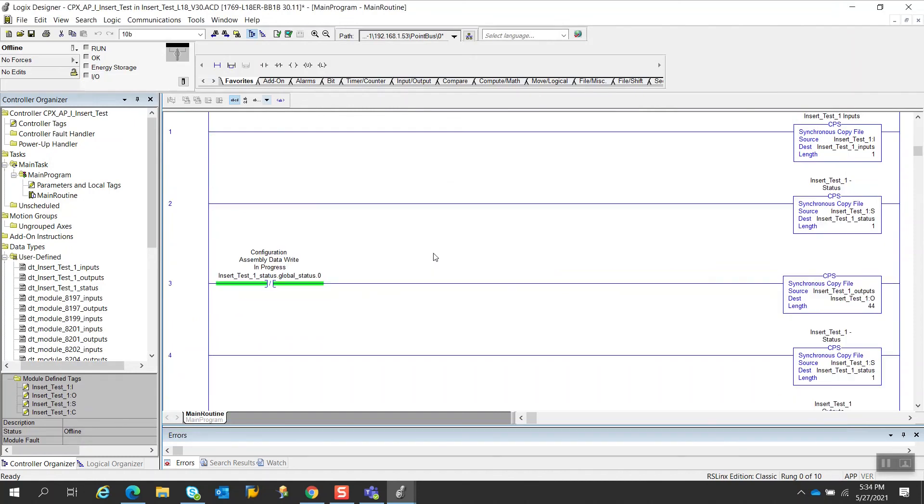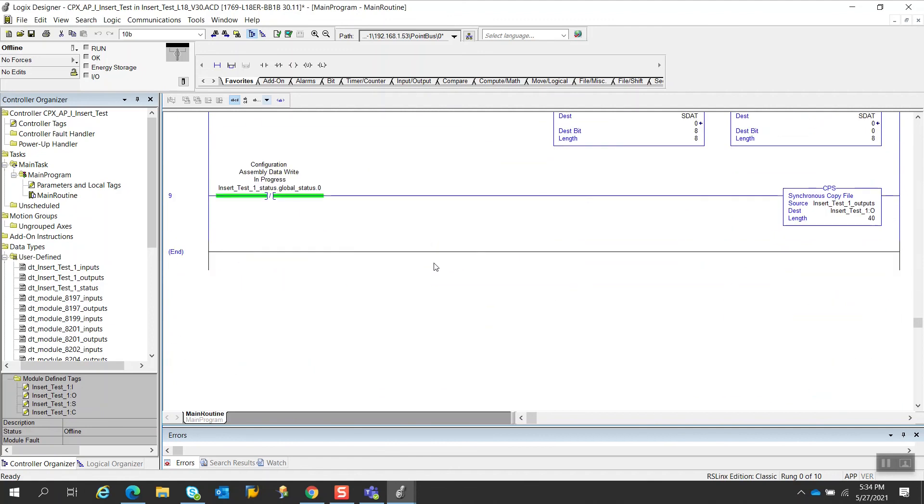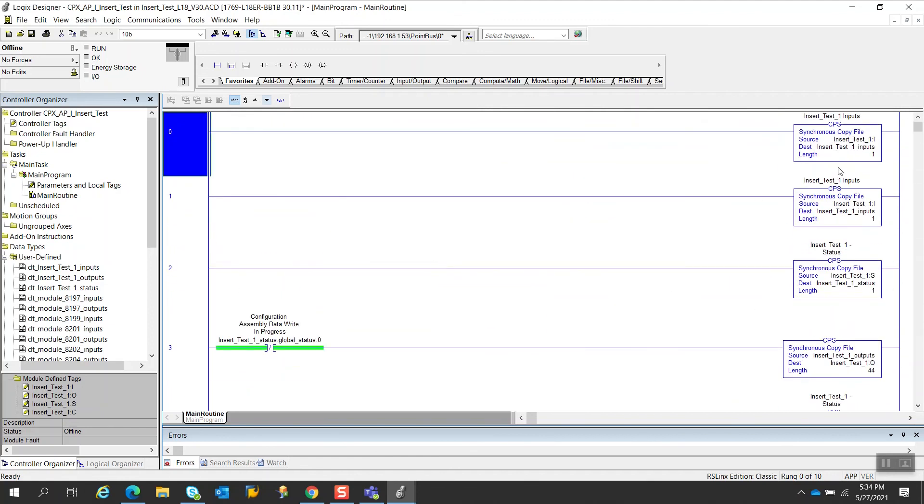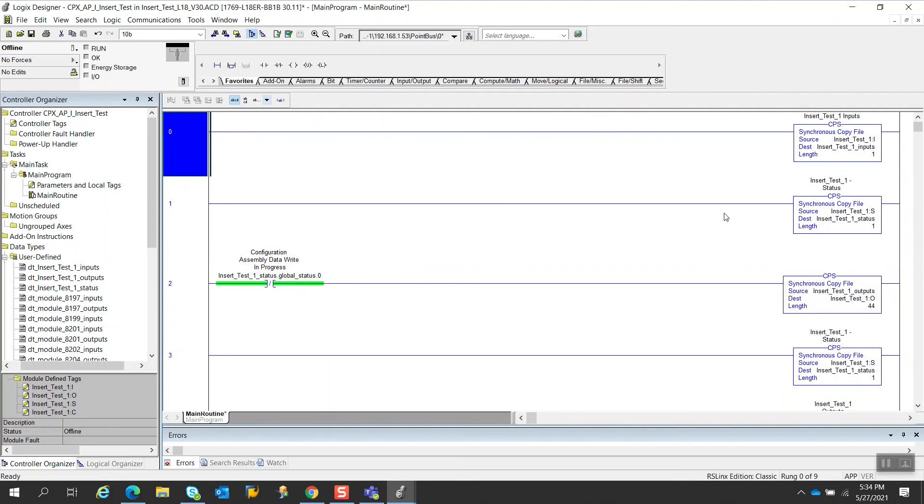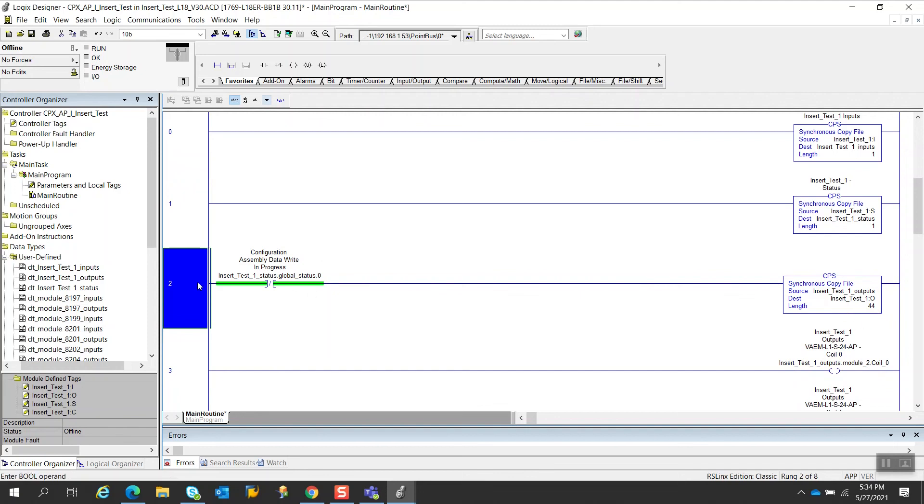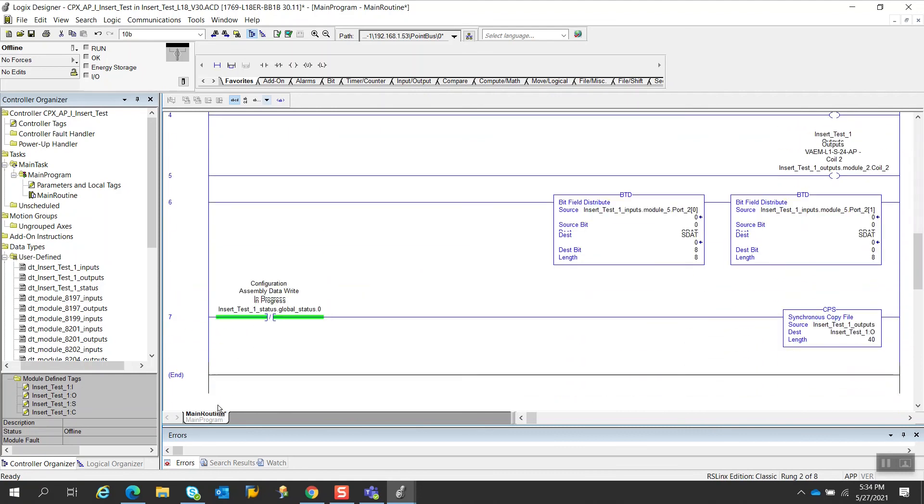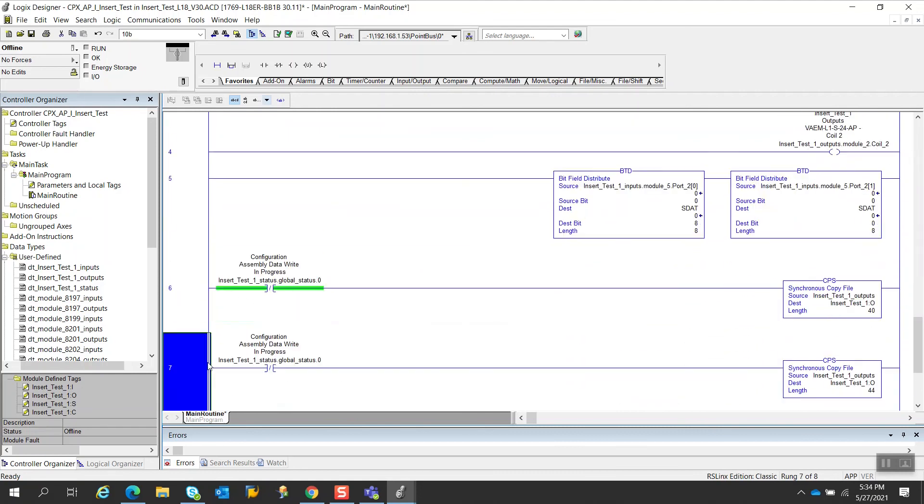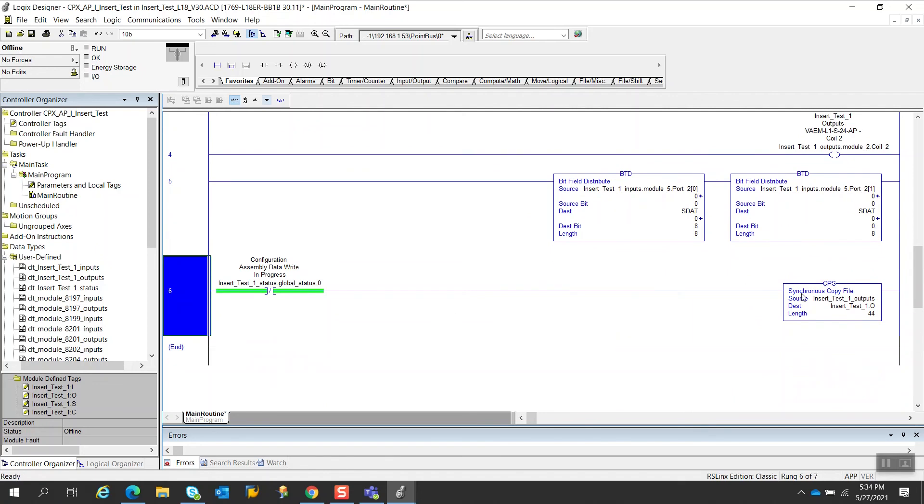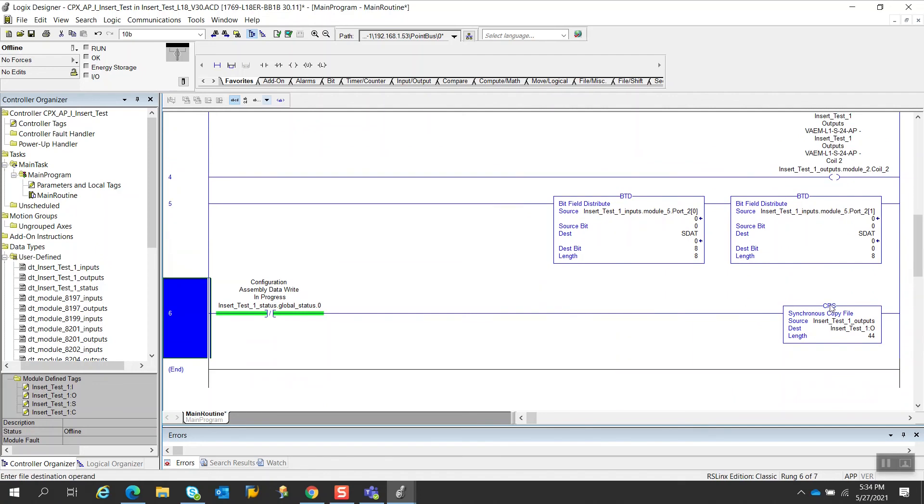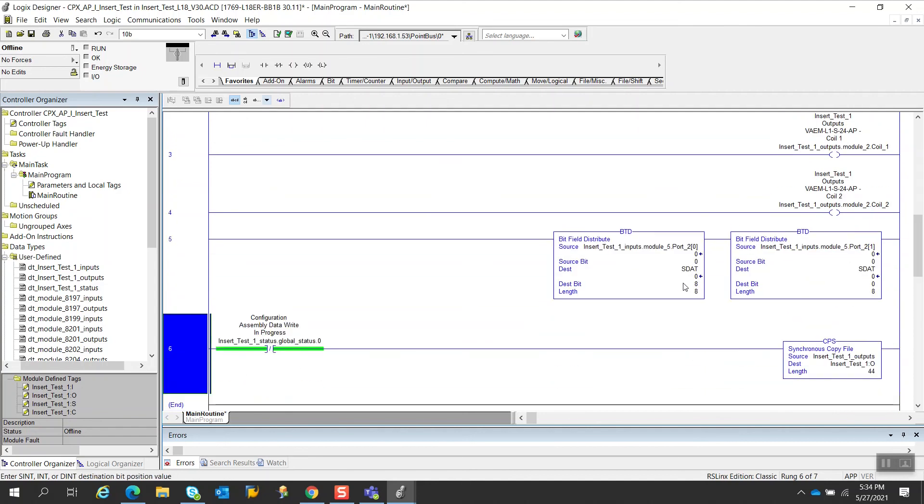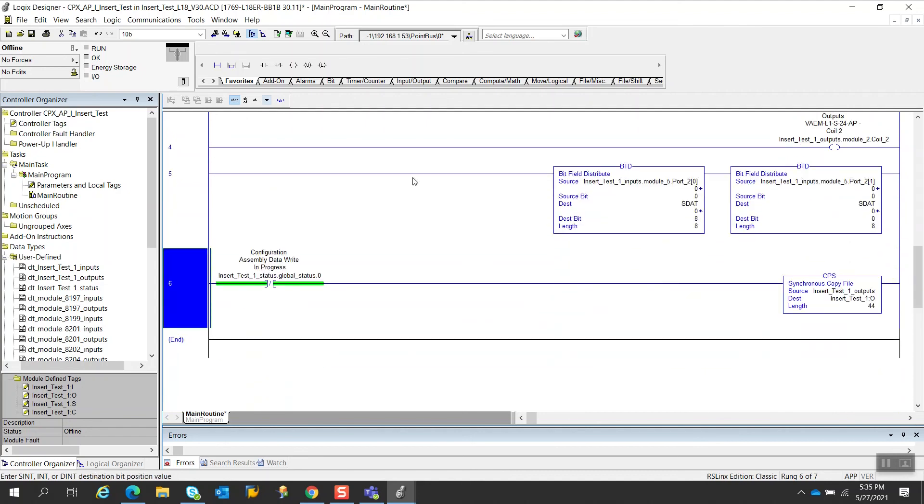So with that import, if I scan through here so far, there are no errors. I do need to delete some of the duplicate rungs. So I'm going to do that right now. This is an input one and I will delete. There should be a duplicate status one that's over here. I'm going to delete that. And very important, this output one here has a new size now, which is 44. I'm going to drag this down to the bottom of my simple project. And I'm going to make sure that I delete the rung that was from the old project that had 40 bytes of output data. So now I have 44.